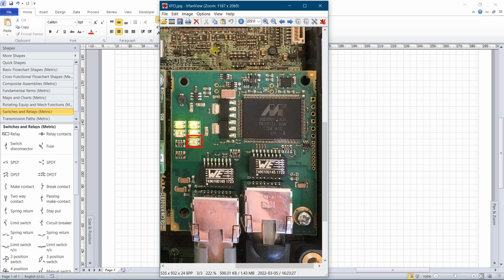If it is off, then communication with the inverter is working without any problems. If the red is on, then there is an error in communication with the inverter. If it flashes twice, it means that process data mapping is invalid. Three flashes mean that there are too many process data parameters mapped.